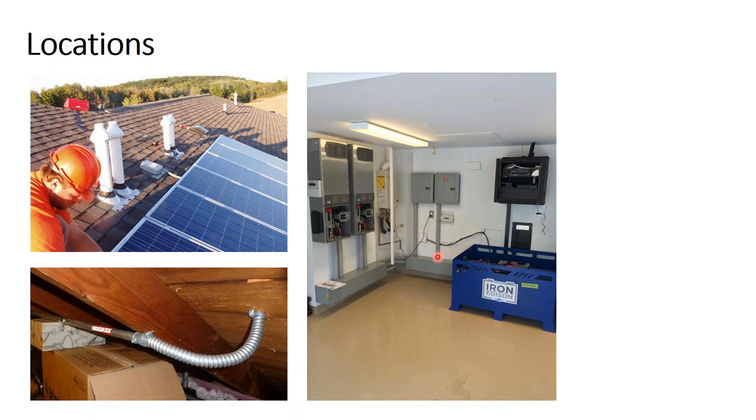And there's code rules of clearance requirements that essentially boil down to, you know, where you have electrical wiring, you can't have other services like plumbing or gas lines in that space. And there's certain offset requirements that essentially boil down to making the space safe to work in. And that includes if you have some electrical equipment up here and some electrical equipment down here, there's even a depth requirement of only about 6 inches offset that you're allowed to do. So it's very easy to get into a code violation when it actually comes to hanging the stuff on the wall.